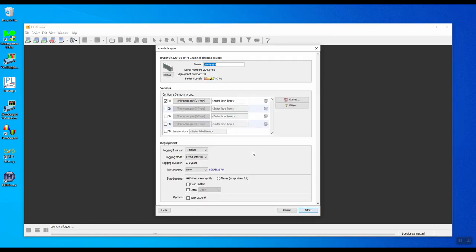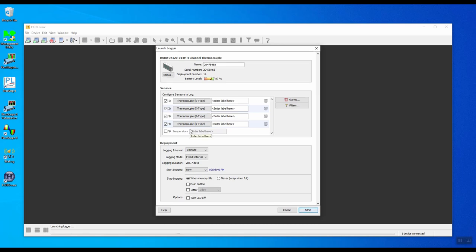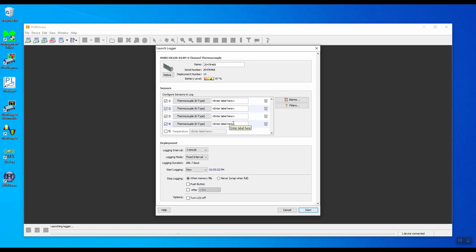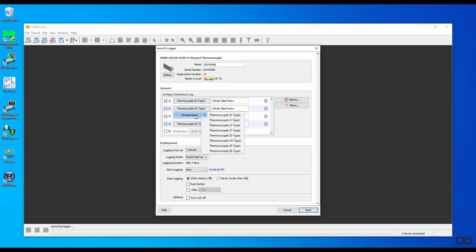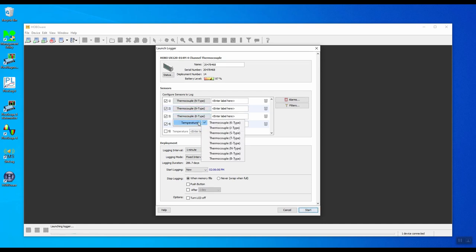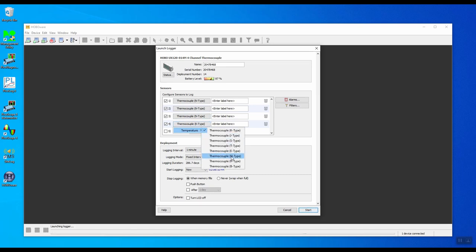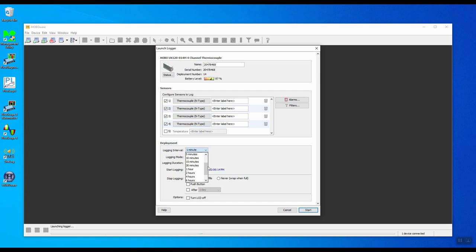We'll configure all four channels and make them all as type N. To enable all four channels, click on the tick boxes next to each channel. The fifth channel is an internal temperature sensor which we will not use in this particular case. Click on each channel, hover over temperature, and select N type. The logging interval can be anything from one second up to 12 hours, but we'll make it 10 seconds.